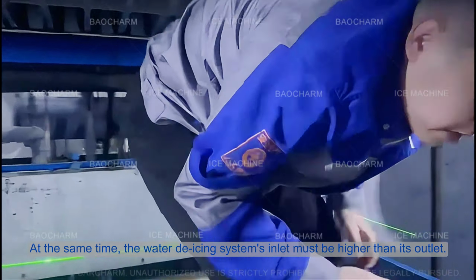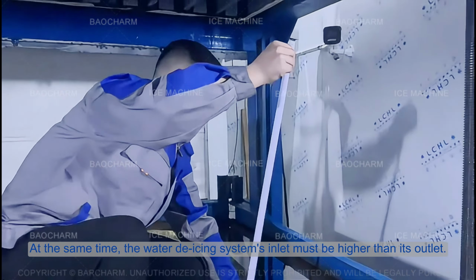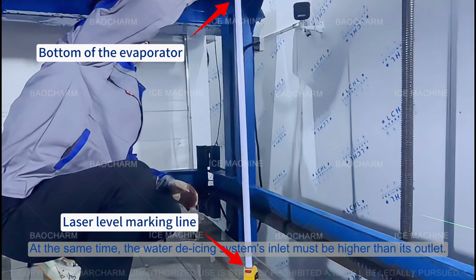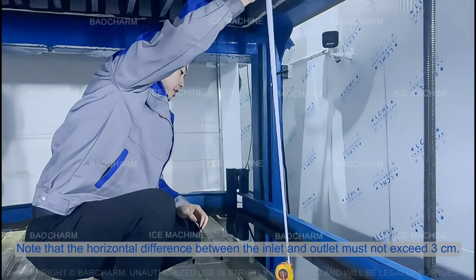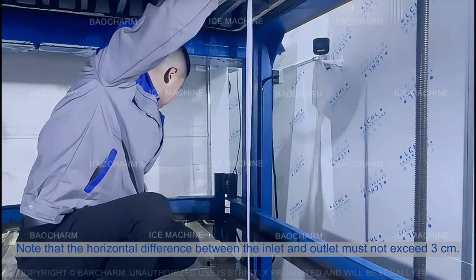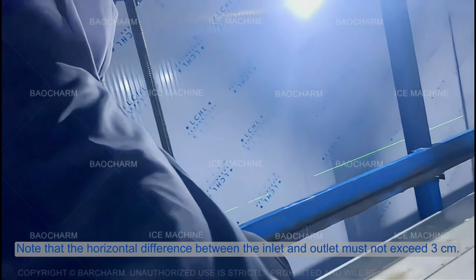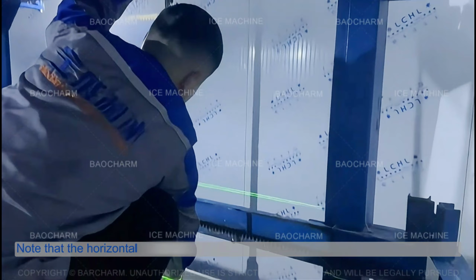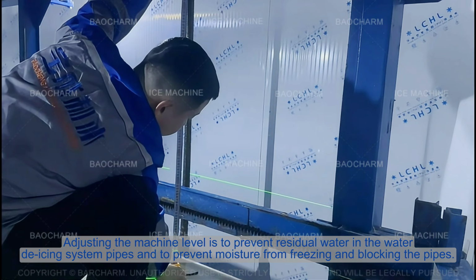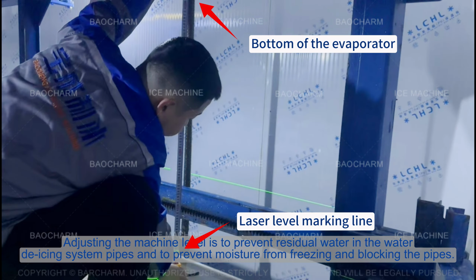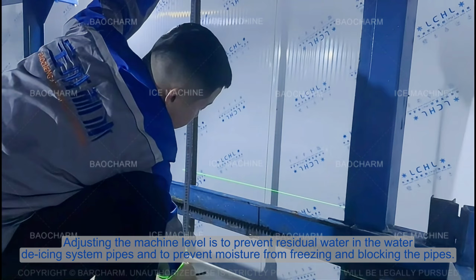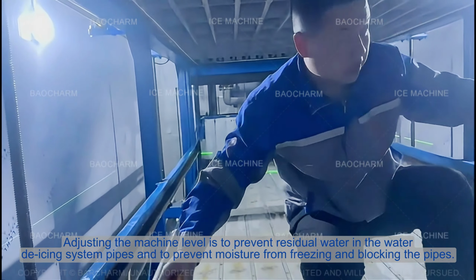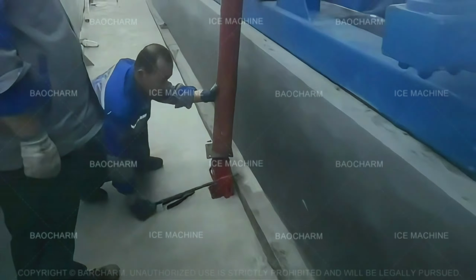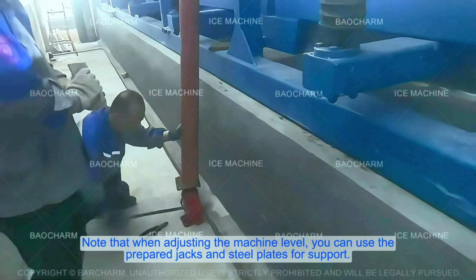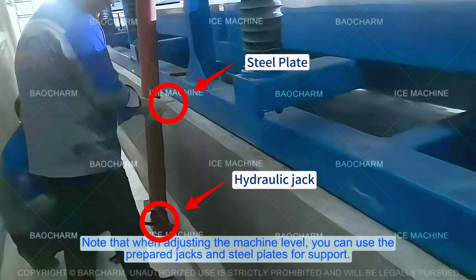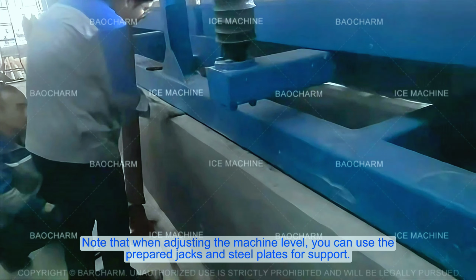At the same time, the water de-icing system's inlet must be higher than its outlet. Note that the horizontal difference between the inlet and outlet must not exceed 3 centimeters. Adjusting the machine level is to prevent residual water in the water de-icing system pipes and to prevent moisture from freezing and blocking the pipes. Note that when adjusting the machine level, you can use the prepared jacks and steel plates for support.